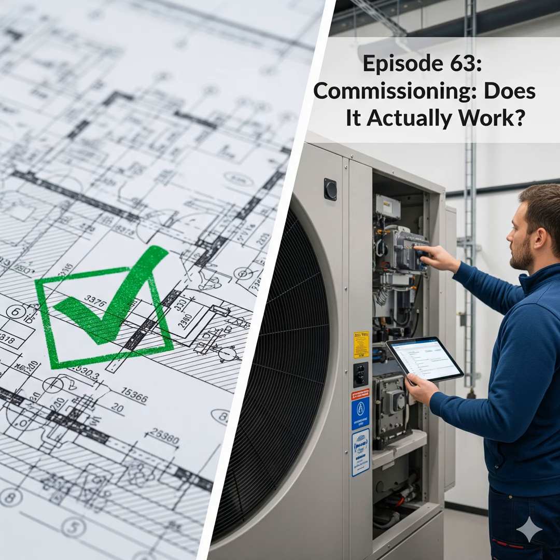Like shutting down air supply in a fire event. We're looking at things like temperature stratification, making sure air is balanced correctly to each space, controlling humidity precisely. It ensures every component talks to each other as designed, and that the system can handle its full range of operating conditions. It goes way beyond just powering something on - it verifies the whole integrated system performs its complex choreography perfectly.